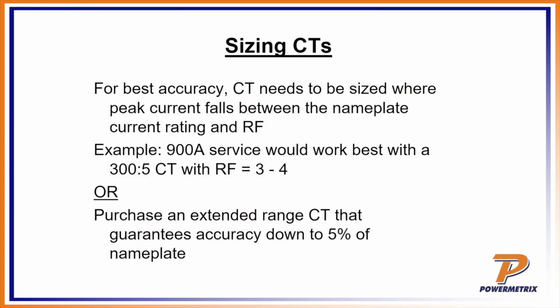If I had an extended range CT, it would go all the way back and grab them, because you can see there it goes all the way down to 5% of the nameplate. So whatever it says on that nameplate, I can go all the way down to 5% with high accuracy. So with one extended range CT, I can hit the low end, and then I get a rating factor and I can hit the high end. That's where we're seeing a lot fewer particular CTs needed out there at the utilities. I can get one that'll cover an awful lot of stuff, right?